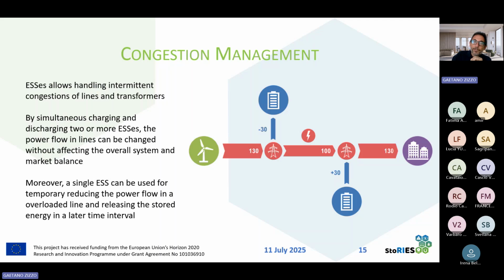Another possible use of storage systems for congestion management is using only one unit, for example the first one, that stores energy in a given hour when we have an excess of production from the wind plant, and then releases the same energy in a later time interval when the production from the wind plant is reduced. In this way, both in the first time interval and in the second time interval, the line here is carrying an adequate power and is not suffering overloads.